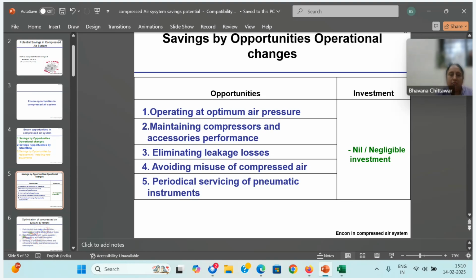That will be recorded. When certain industries, they are doing it actually to that extent. Remember, Hyundai and other car industries like kWh per car, now they started recording CFM per car and water liters per car, fuel per car. They are recording, they are monitoring. So that since power cost is very high, compressor cost is very high, they started monitoring and leakage losses. So I'll come back to leaks later.